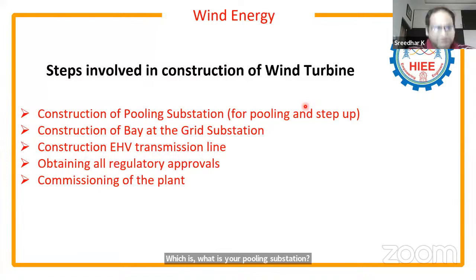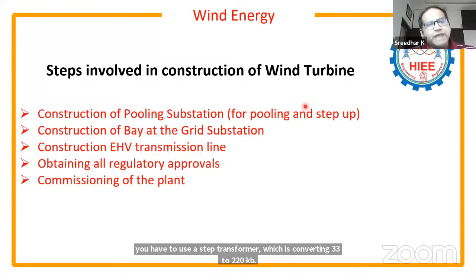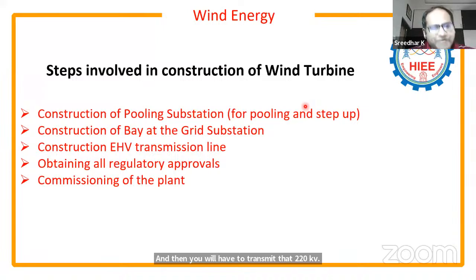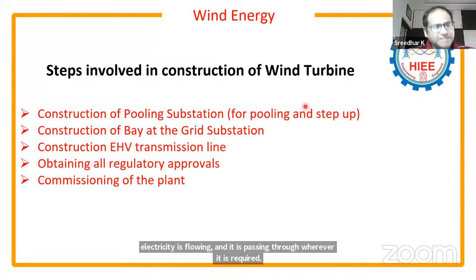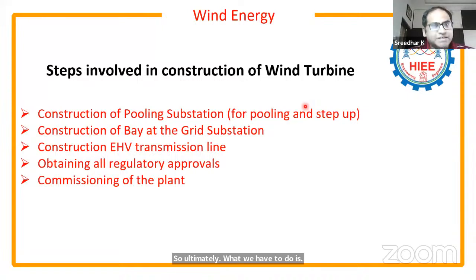If you want to step up to the next level, say transmit at 220 kV, you use a step-up transformer converting 33 to 220 kV, then transmit through a 220 kV EHV transmission line and evacuate at the grid substation. From there, the electricity flows wherever it is required. Ultimately, once we generate the power, we have to evacuate it at the grid substation.